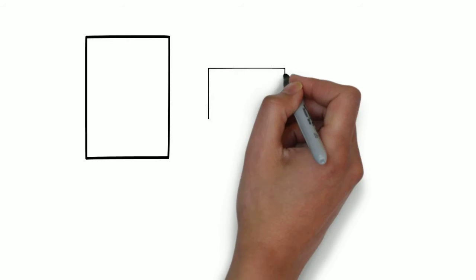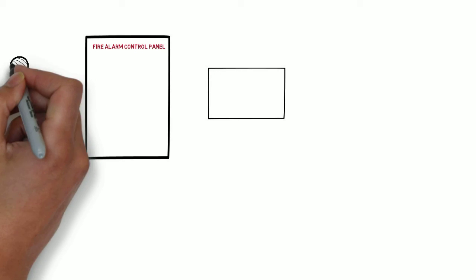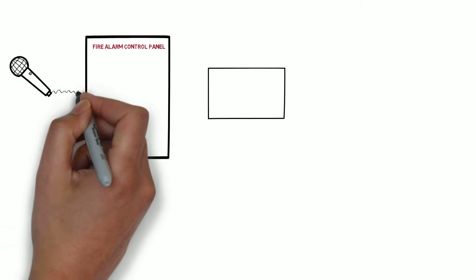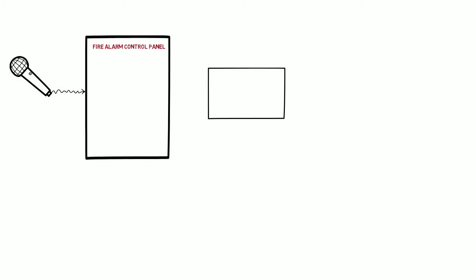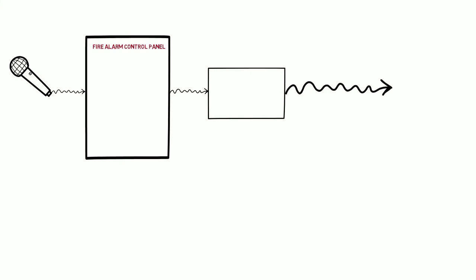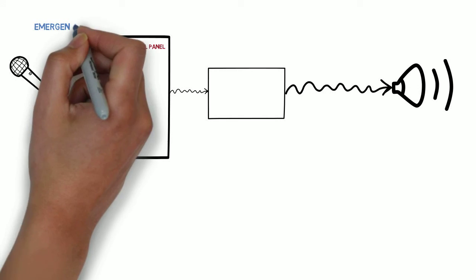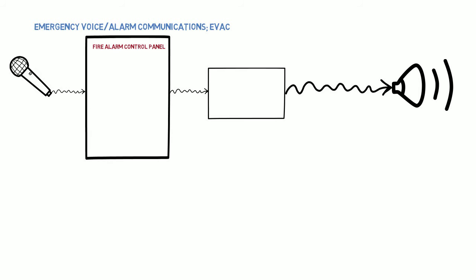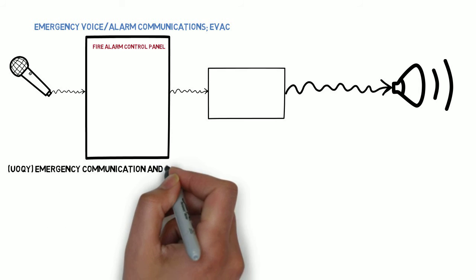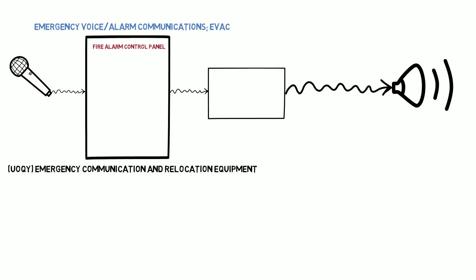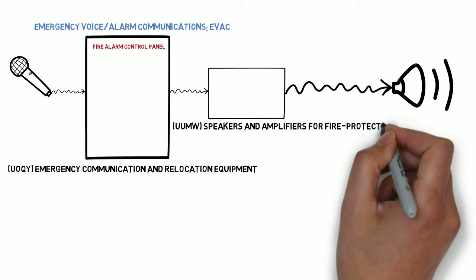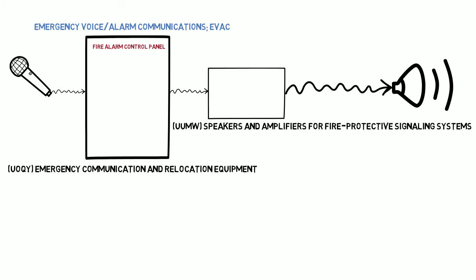A system that notifies people at the protected premises that there is a fire and provides instructions and evacuation signals via live or recorded messages is an emergency voice alarm communications type or EVAC. These are listed under UOQY emergency communication and relocation equipment. The amplifiers are listed under UUMW speakers and amplifiers for fire protective signaling systems.